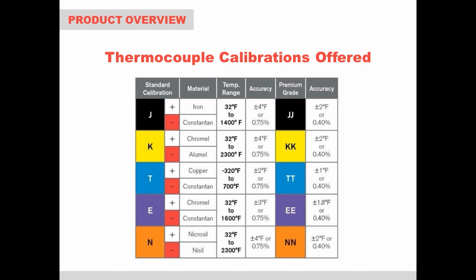Following Seebeck's discovery, over the years different dissimilar metals were used, and a number of standard combinations emerged and are now industry standards. Smart Sensors offers the following 5 standard calibrations, with type K and J being the most common. Each calibration has an industry standard color code for the lead wires, as shown in the above chart, along with a published limit of error for each type, including the premium grade, which uses higher purity grades of the 2 conductors used in each calibration. For each degree measured, the thermocouple, based on the metals used, will generate a millivolt output proportional to the temperature change. The accuracy spec is solely dependent on the purity of the metals used and the uniformity of the manufacturing process of the MI cable.